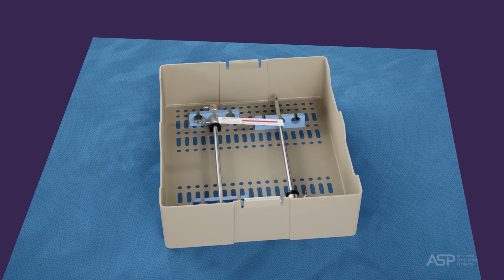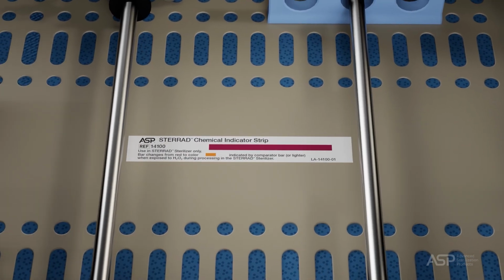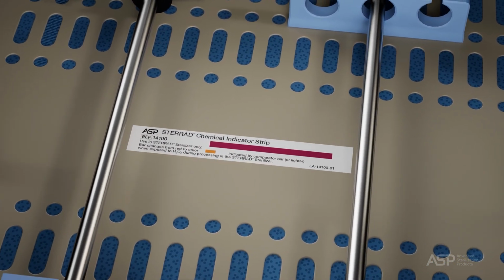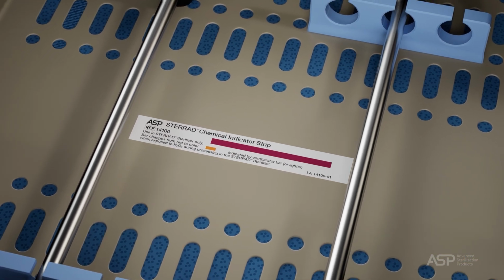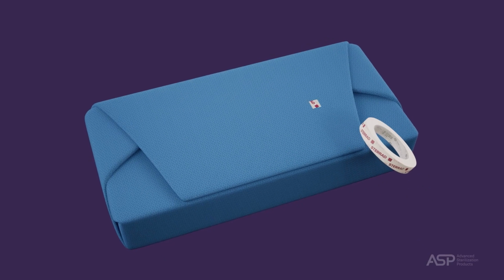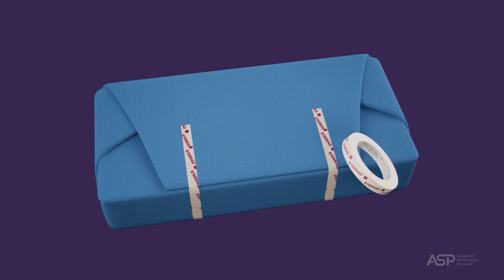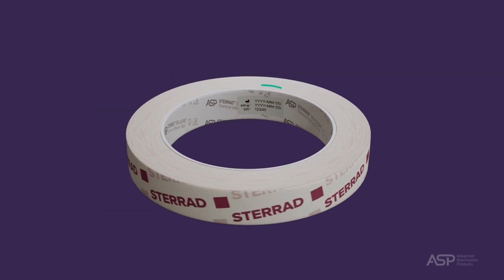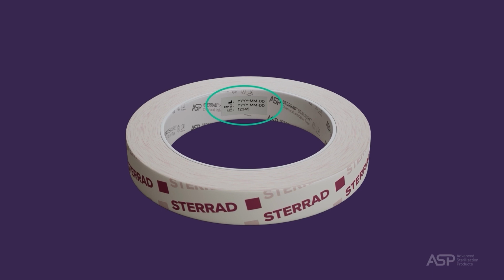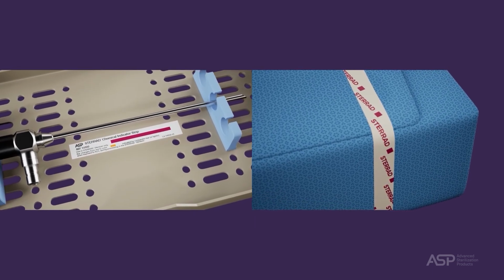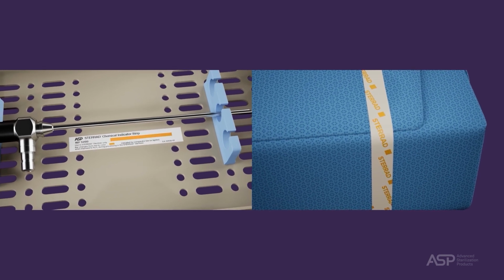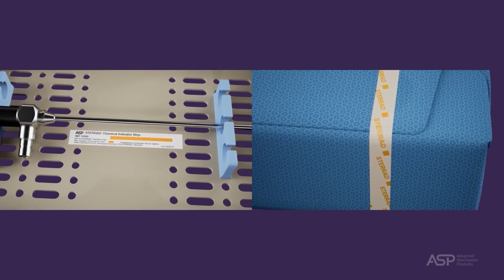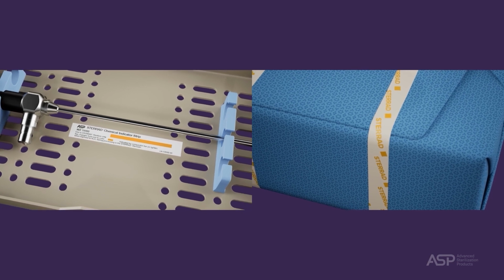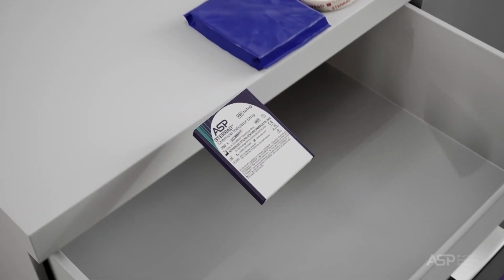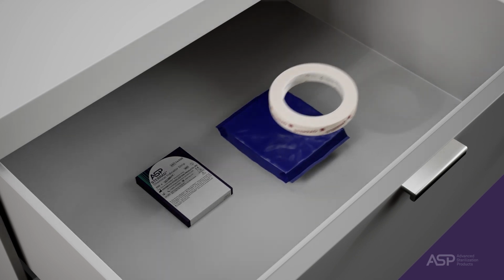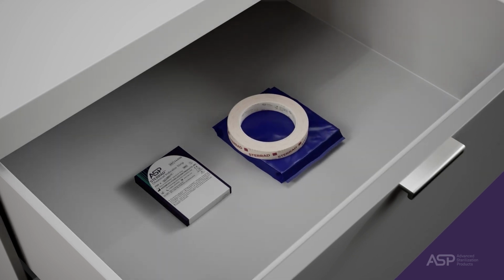Place a STERRAD chemical indicator strip inside the tray container or pouch. Notice that the lot number and expiration date are not printed on each individual STERRAD chemical indicator strip. Secure all wrapped trays with SealSure chemical indicator tape. The expiration date for the SealSure chemical indicator tape is located on the inside of the roll. The STERRAD chemical indicator strips and SealSure chemical indicator tape change from red to yellow when exposed to hydrogen peroxide. Yellow indicates processed and red indicates unprocessed. Be sure to store the STERRAD chemical indicator strip indicator box and SealSure chemical indicator tape away from heat and light.